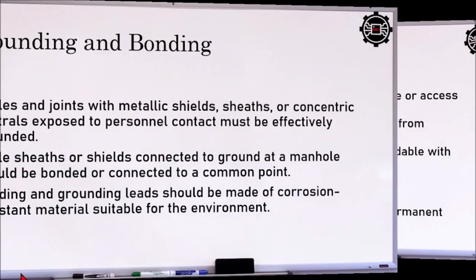Okay, so grounding and bonding. So cables and joints with metallic shields, sheaths, or concentric neutrals exposed to personnel contact must be effectively grounded. So if our cables are metallic shields, tapos sheets or ang kanyang neutral are concentric, which is exposed doon sa ating personnel, so they must be effectively grounded. Then cables or sheaths connected to ground at a manhole should be bonded or connected to a common point.